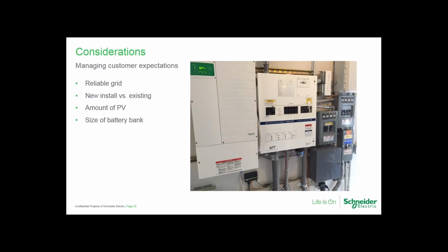So when you're AC coupling and using those grid interactive functions, once it goes to AC pass-through and stops charging, the batteries are going to be resting. They're not going to have any load on them, but also no charging source applied to them. A 48-volt battery at rest is typically going to be around 50.8, maybe 51 volts. That's why the LEDs are showing what most would consider a partial state of charge, but it's really not. That's where the Connect's battery monitor comes in handy. It's going to reflect the actual percentage of current that's been replaced into the battery, and it's not going to be reliant on whether you're at a resting voltage or being held at a float level.